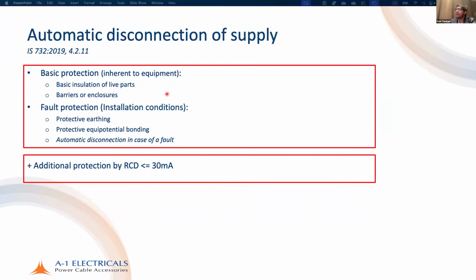Now, this is a little bit about ingress protection. A subject of quite a lot of interest amongst people is earthing. We all know that the protective measure of automatic disconnection of supply is the most common for low voltage electrical installations. There is basic protection, fault protection, and additional protection. Crucially, fault protection is provided by protective earthing, protective equipotential bonding, and automatic disconnection in case of fault. Today, I want to focus a little on protective earthing and automatic disconnection in case of a fault.